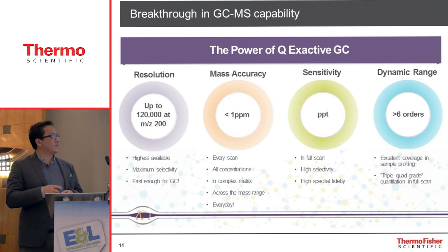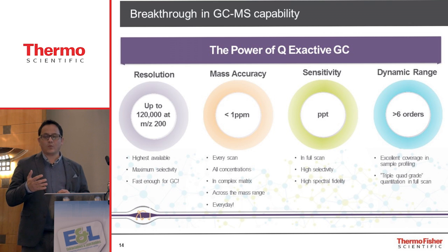We also have an exceptional level of mass accuracy. I've got a few slides where I deep delve into this, but we in routine run at 1 ppm mass accuracy, and the value of that is explained in the next few slides.